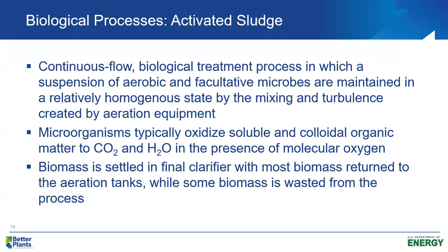The organic matter that is channeled into the energy reaction is converted to CO2 and water primarily. That organic matter is basically destroyed because we're converting it into gaseous end products. But the biomass that goes to the secondary clarifier, final clarifier, we settle it to produce a high quality effluent. And again, most of it will be returned back to the aeration tank in the return sludge.